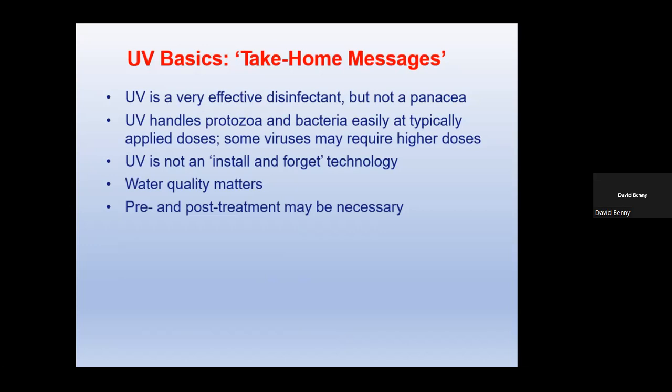It handles bacteria at the normally applied doses. But if you need to inactivate viruses, based on the chart that I showed, you may have to have a higher dose. It is not install-and-forget technology, as has happened in many small installations in Trinidad and Tobago.